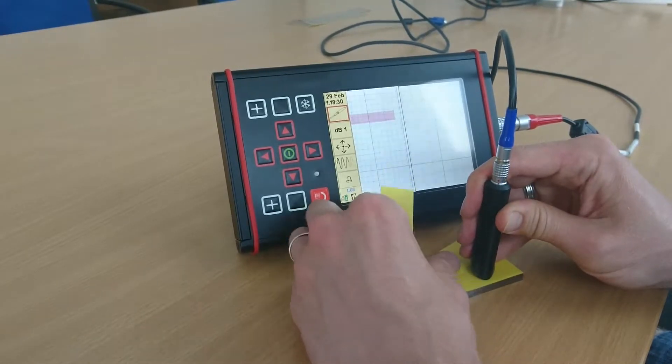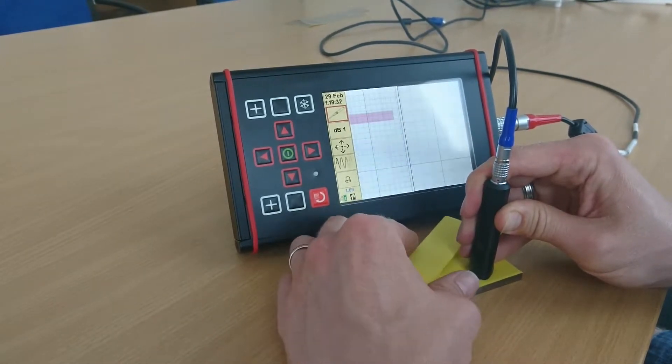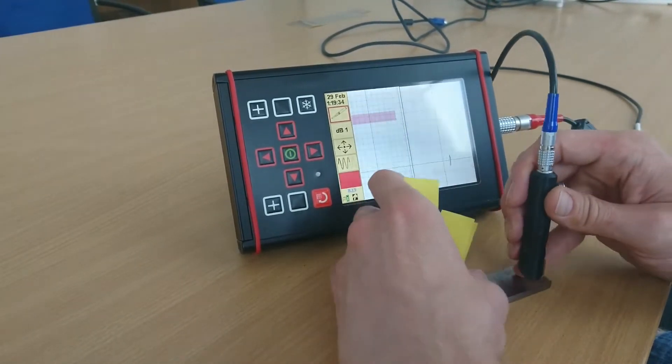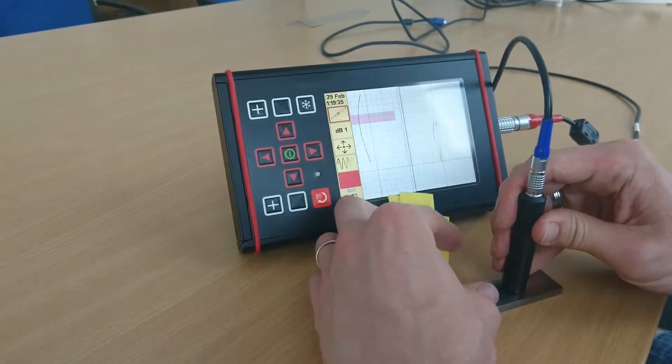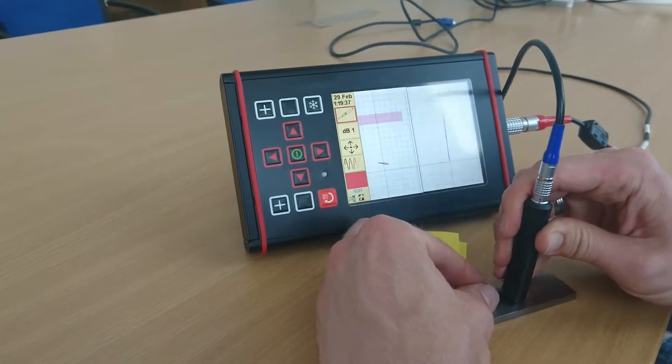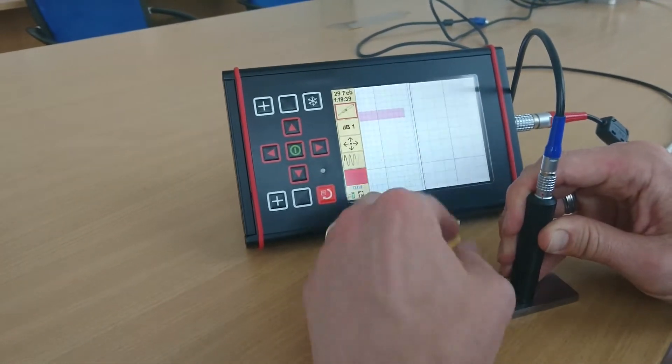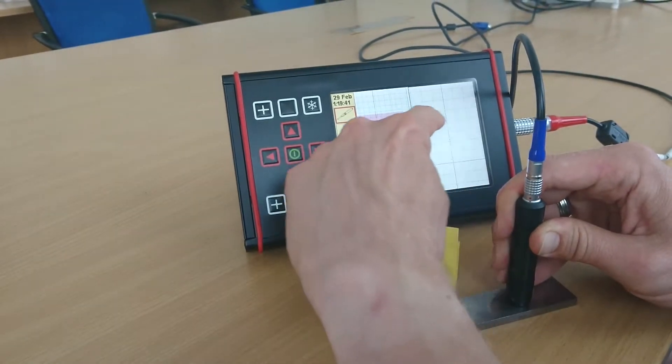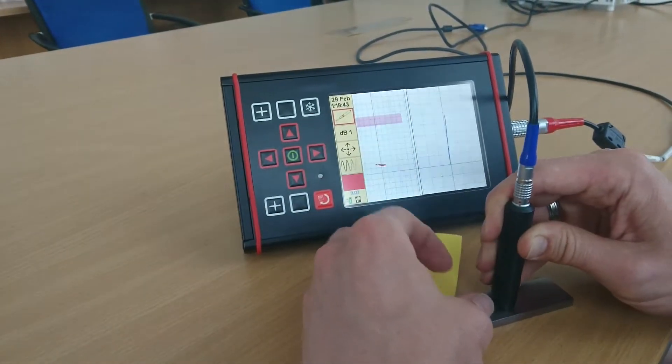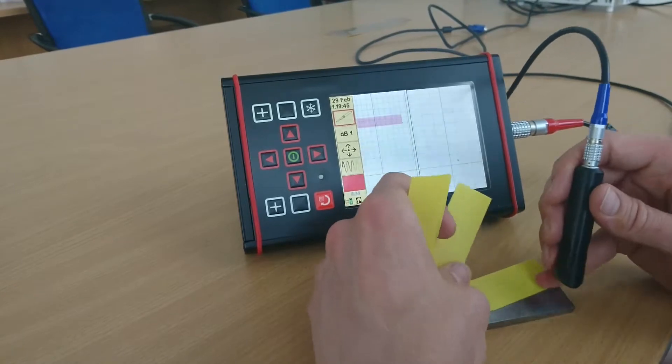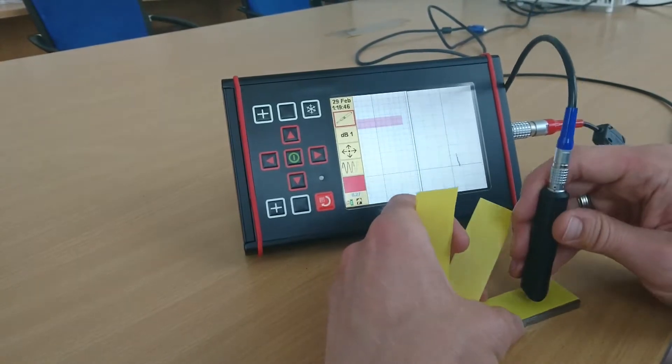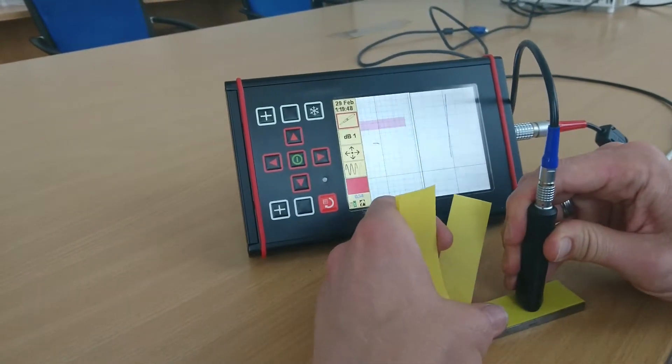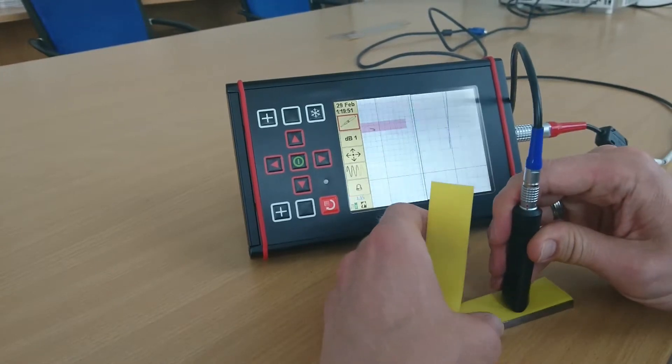Okay, now go over the defect. So this side, if the defect is reaching this line here, which is the 40% point with the shim, you see that it's going slightly high. We can sort that out in a second.